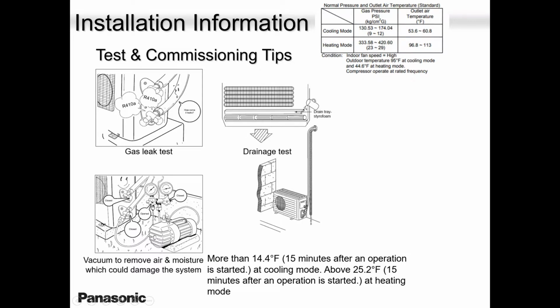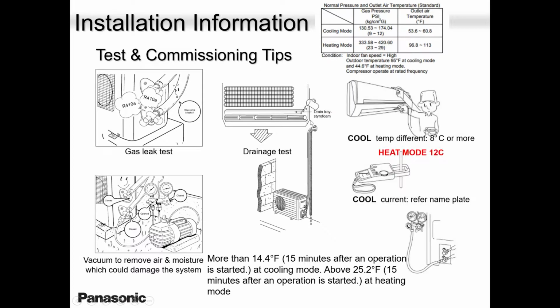Vacuuming, always remember 500 microns and below, with a short hose length of 15 feet, 10 feet. Even below 300 is the best thing that you can achieve. Always test your drain, even if you're installing this unit in winter time. Always make sure you test your drain and make sure what is coming out and you're happy. Okay, always block the hole with proper silicone, because when air goes in, it can cause the unit to overheat in heating or go to sleep in cooling. So always keep that in mind, guys.